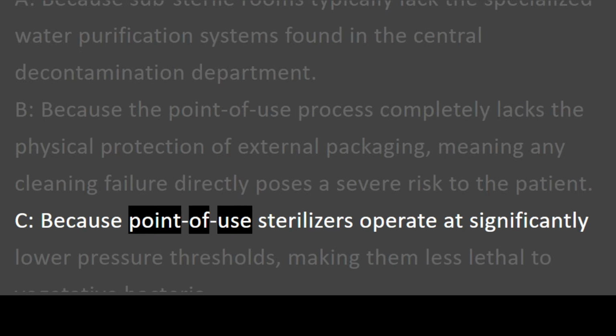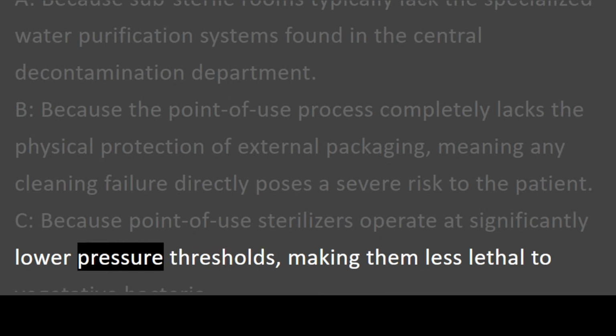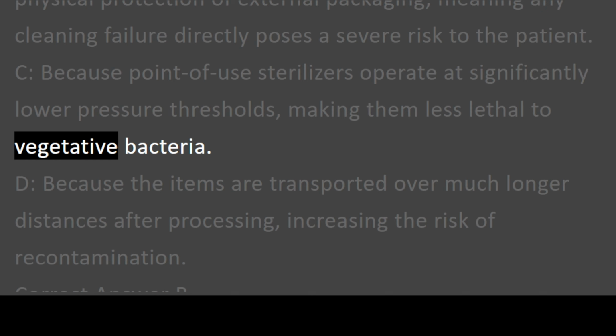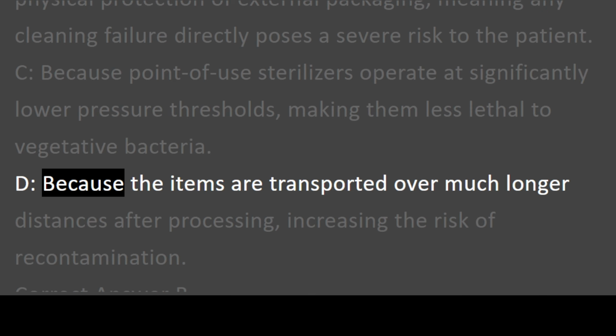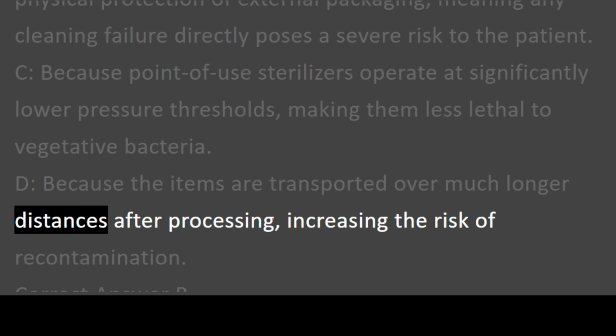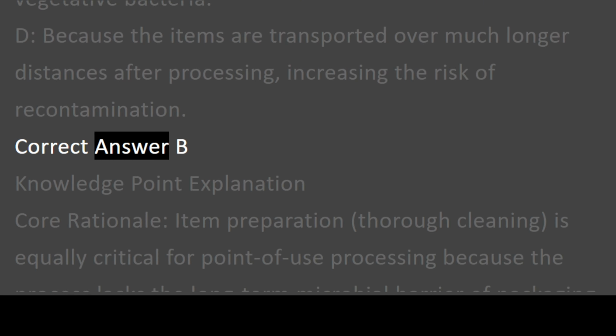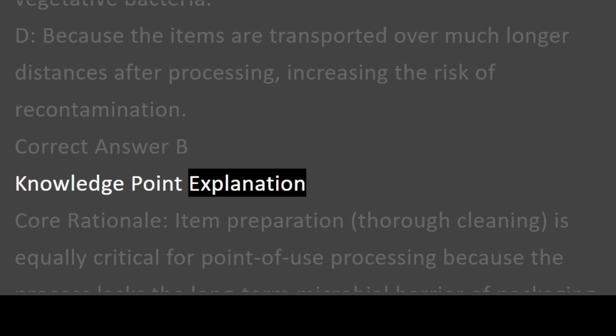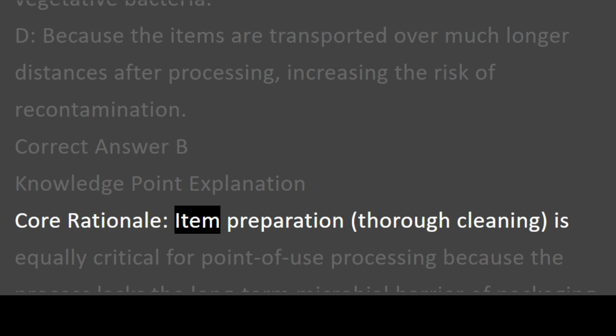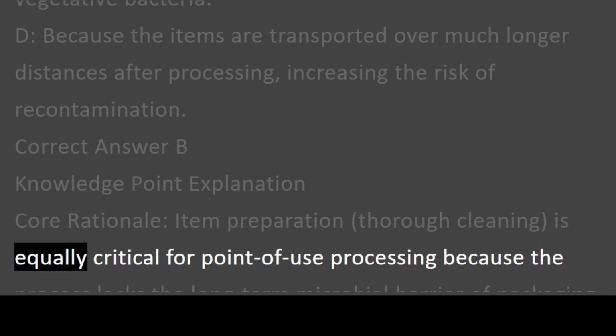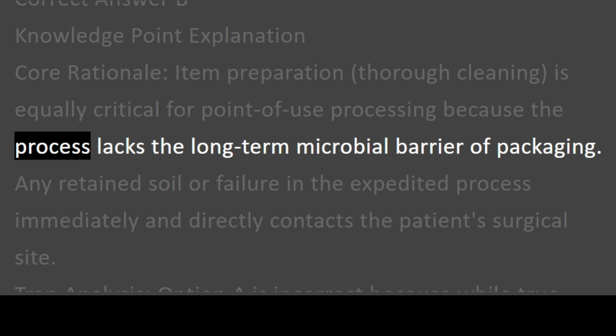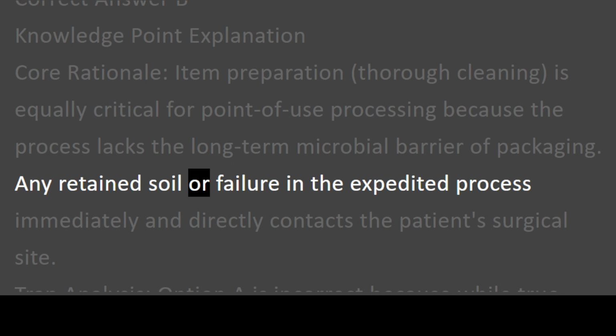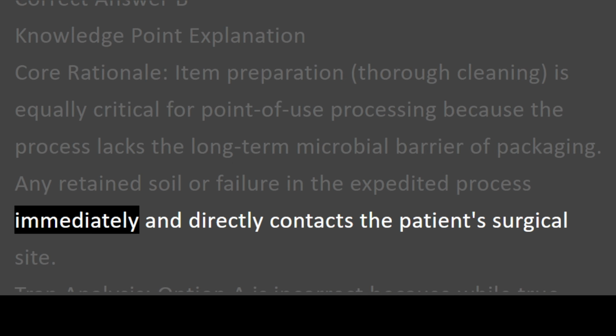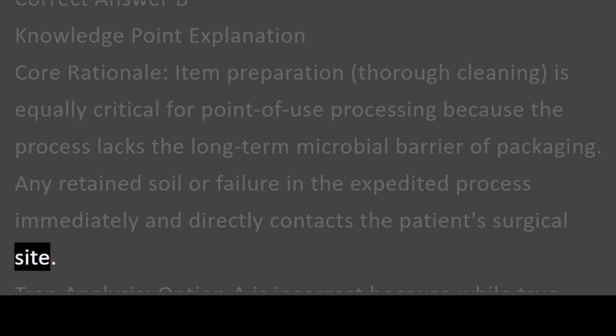C. Because point-of-use sterilizers operate at significantly lower pressure thresholds, making them less lethal to vegetative bacteria. D. Because the items are transported over much longer distances after processing, increasing the risk of recontamination. Correct answer B. Knowledge point explanation. Core rationale: item preparation, thorough cleaning, is equally critical for point-of-use processing because the process lacks the long-term microbial barrier of packaging. Any retained soil or failure in the expedited process immediately and directly contacts the patient's surgical site.